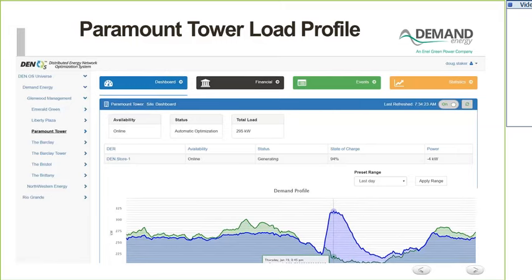But because it only measures demand from 8 a.m. to 10 p.m., we can do things like load the battery up in the middle of the night - that's what's going on with that big spike, that's us refilling the battery system. Then you'll notice as the building starts to come to life - right here at about 6 a.m. - you see how the load starts to ramp up.